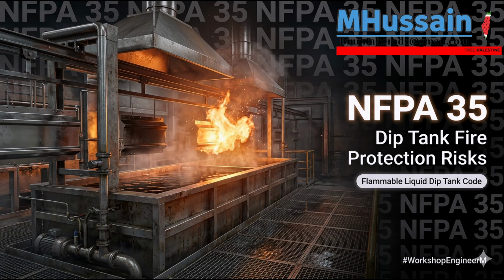And dry nitrocellulose is a disaster waiting to happen. It's a bomb. The standard even dictates the exact protocol for sweeping the floor. Really? Sweeping? Yes, you cannot just take a broom, sweep up spilled nitrocellulose dust, and throw it in a standard plastic trash can. The friction of the broom itself is a hazard. Oh my goodness. Sweepings must be immediately wetted down with water or solvent and placed in a specialized covered metal container.